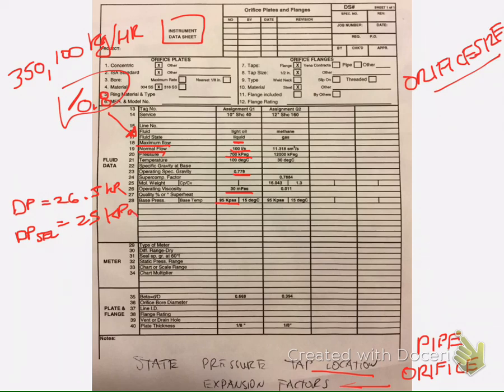And now it's asking for our inside pipe diameter. And to simplify things, since I don't have my book with me, if I don't, on any test or exam, state the inside diameter, just use the measurement given. So 10 inch, schedule 40, and our program's asking for it in millimeters. So we need to multiply by 25.4, so 10 times 25.4, which is going to be 254 millimeters. We key that in, and it gives me a DP norm of 16.